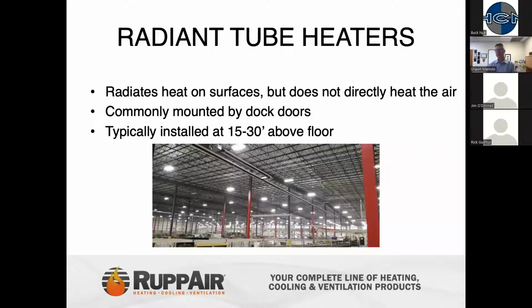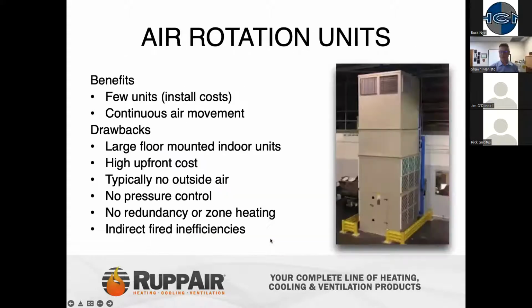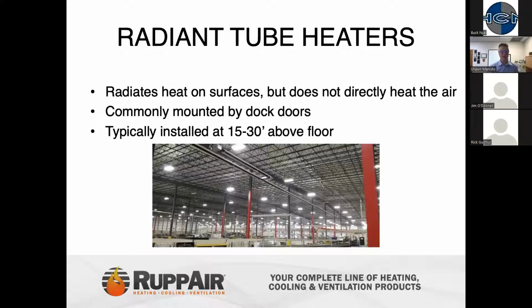The last indirect fired source is going to be radiant tube heat. Radiant tube heat is basically radiant heat off surfaces. Basically, it's going to radiate a temperature across onto a surface. It does not do any direct heating of the air, but instead it heats surfaces. Commonly mounted in dock door areas. One thing I'll say about radiant tube heat, this is a very good means of, if you're trying to hold a moderate temperature in a warehouse, maybe down to 50 degrees, but you want to have some spot heating where you have workers or dock areas, this is a big benefit product.